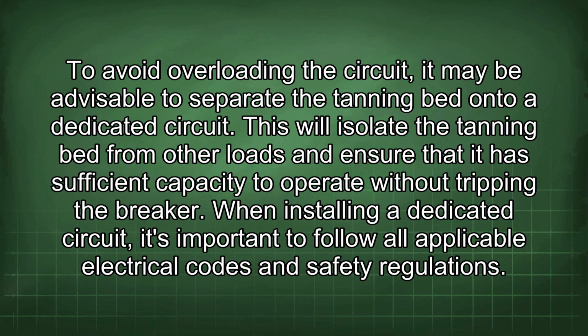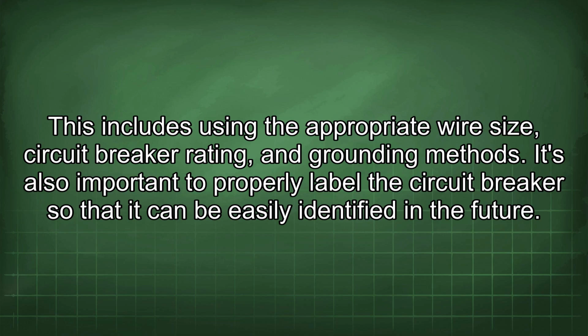This will isolate the tanning bed from other loads and ensure that it has sufficient capacity to operate without tripping the breaker. When installing a dedicated circuit, it's important to follow all applicable electrical codes and safety regulations. This includes using the appropriate wire size, circuit breaker rating, and grounding methods. It's also important to properly label the circuit breaker so that it can be easily identified in the future.